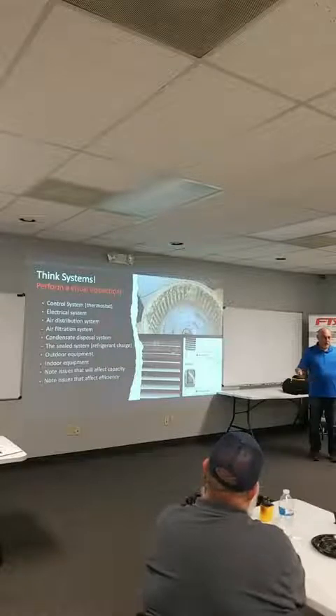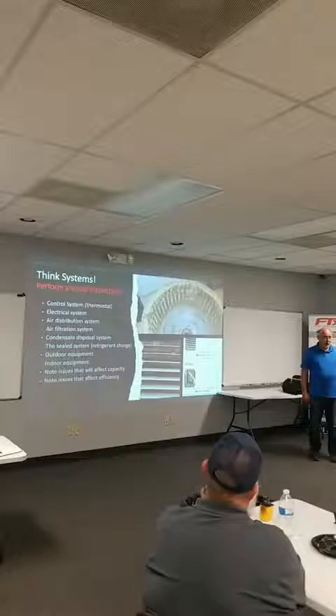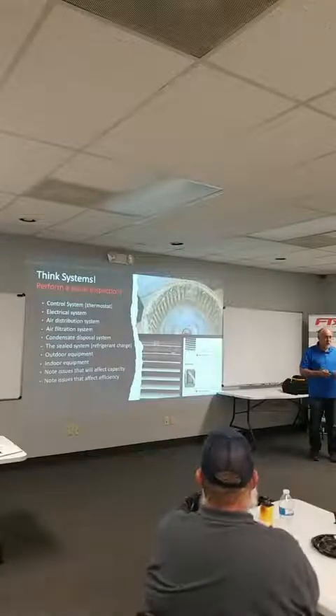You might pull it out and clean underneath the condenser or whatever, but you're never gonna tap into a sealed system. It's the first thing that 90% of guys do in our industry, they hook gauges up to the system, because when we were in school, they said, your gauges are your most important tool, you know, and you gotta have gauges hooked up to the system. It's like, bullshit. You don't have to have gauges up ever. You should never, ever hook gauges up to a system. That's an absolute last resort.